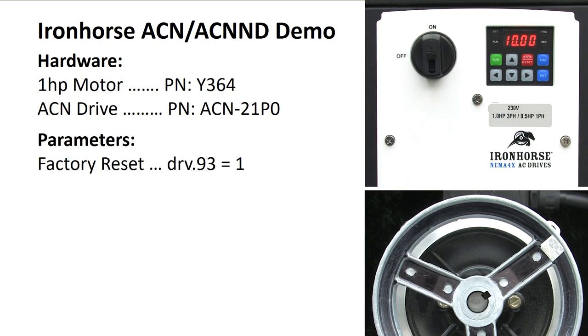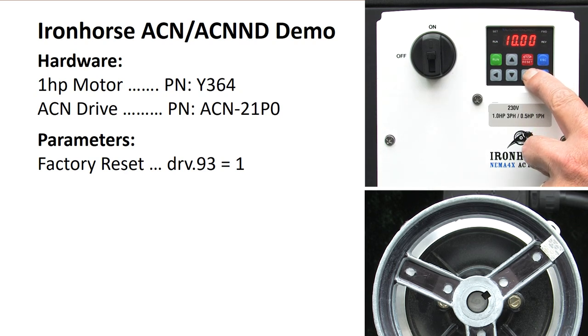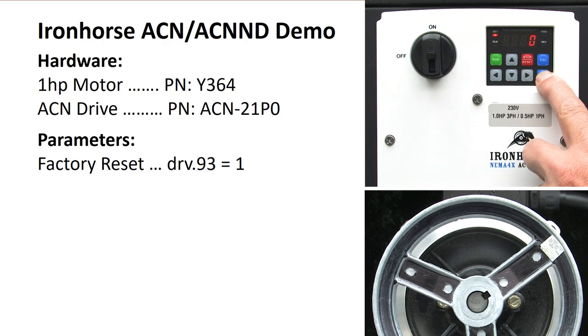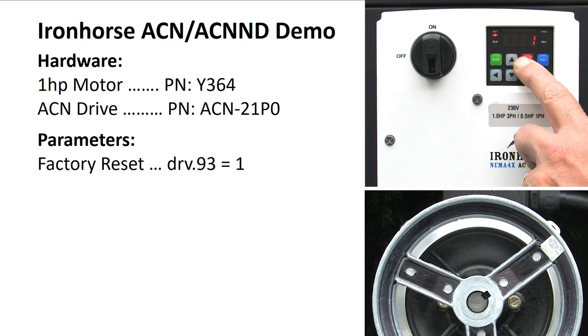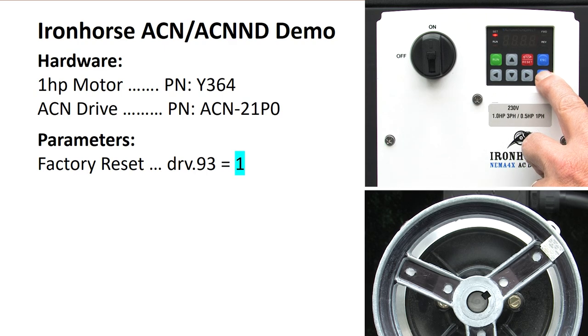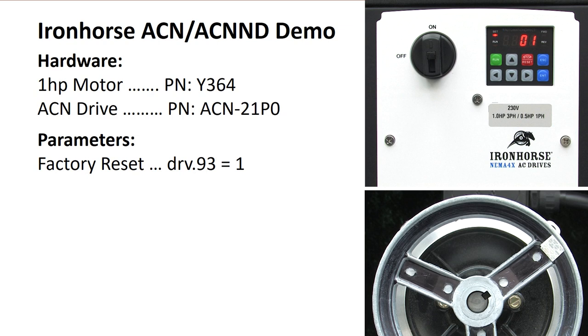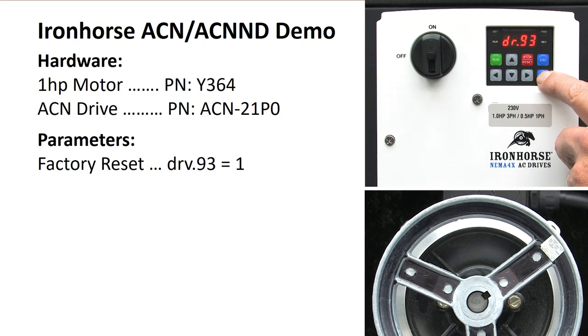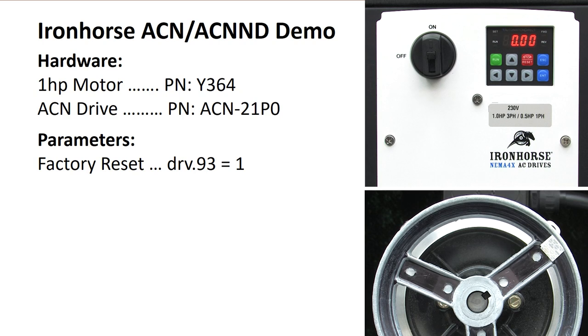Let's reset the drive to factory default so you know exactly where I'm starting from. Just right arrow over to the drive parameter group. I'll down arrow to parameter 93 and select that by pressing the enter key. Change its value to a 1 and enter that. It blinks to ask you to verify that that's what you wanted and to give you one last chance to change your mind. If it isn't what you wanted, hit escape to get out. Now it only blinks for a few seconds so if it stops, hit enter to get it blinking again. This is what we want so I'll hit enter while it is blinking to accept it. Hit escape to get back to the main frequency display.